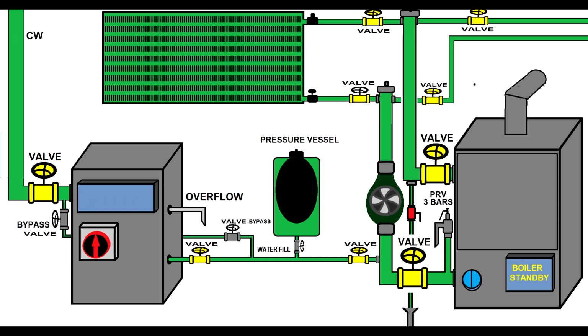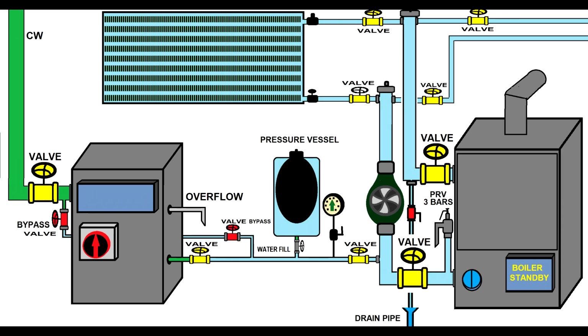You'll open all the valves in your installation. When you fill the tank for the first time, obviously you will turn on the bypass valves. You don't want to stress the pressurization system pumps. It's pointless. And also you will open the purge valve. You will see near the boiler a little valve that changes color from red to yellow, so you'll have a complete circuit. You eliminate all the air. Obviously, the system will be provided with air eliminators that will remove the rest of the air in the installation.